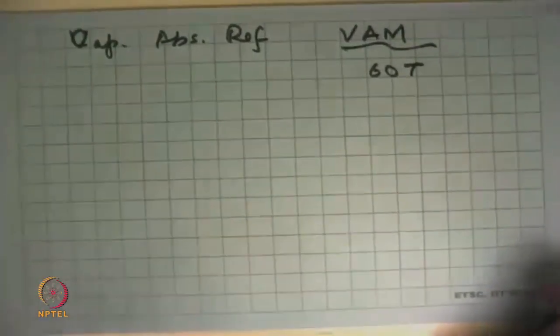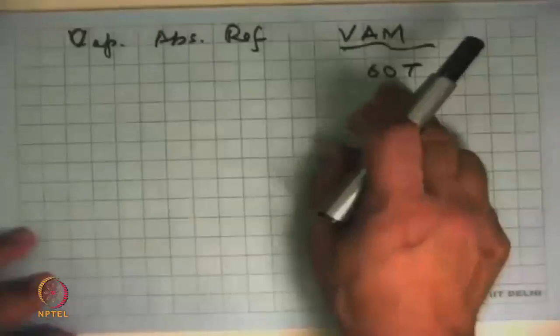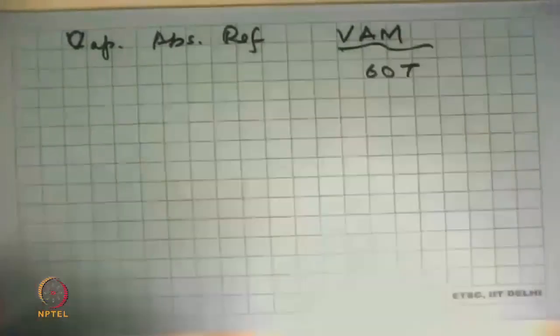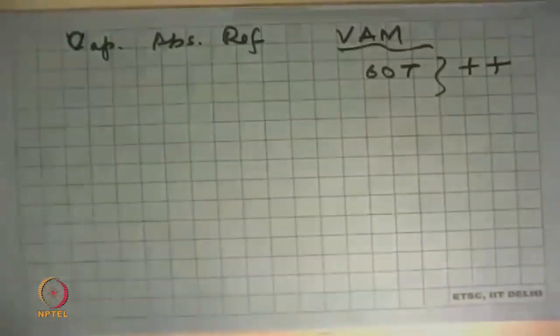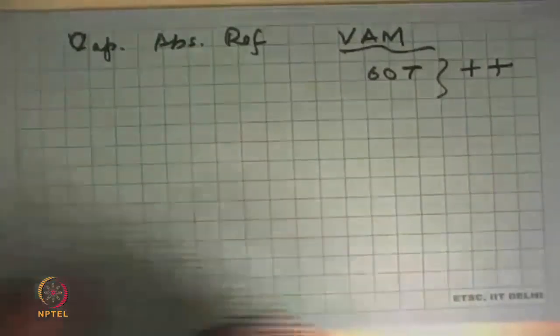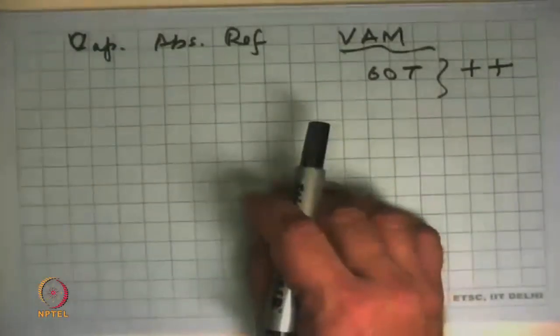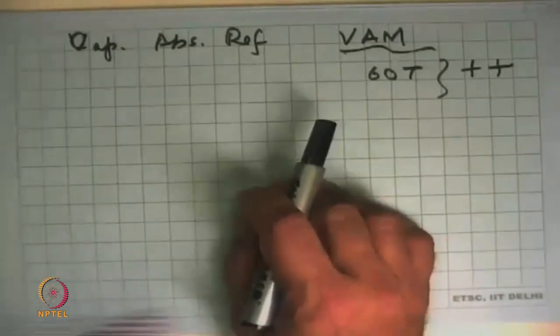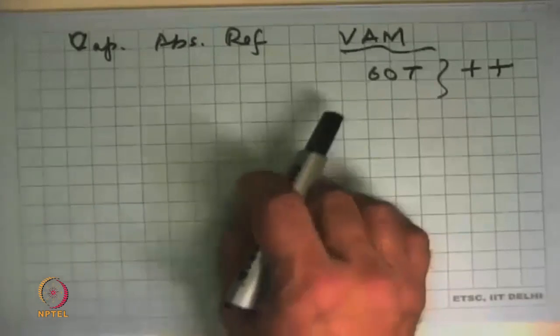If you have a waste heat source, they are very good options because the electric power consumption is 1/10 or 1/20th that of a vapor compression system. So energy efficiency wise and carbon footprint wise, these are great, but the engineering is not at all easy in this case. We do not use conventional cycles. We take water and dissolve it in a salt, and then we pump the solution, so the work required for pumping is very small. Then we heat it to get the high pressure vapor back, condense it, and use it as the refrigerant.